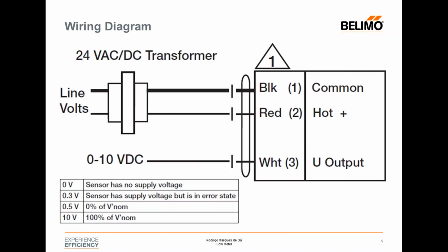In the bottom part we also have a table with some useful information. At 0 volt, the sensor has no supply voltage. At 0.3 volts, the sensor has supply voltage but is in an error state, which could be caused by air bubbles or other installation issues. At 0.5 volt, it means zero flow, zero percentage of flow, or your flow meter is installed in the wrong direction, as I said before. And 10 volts is full span, so 100% of the span.